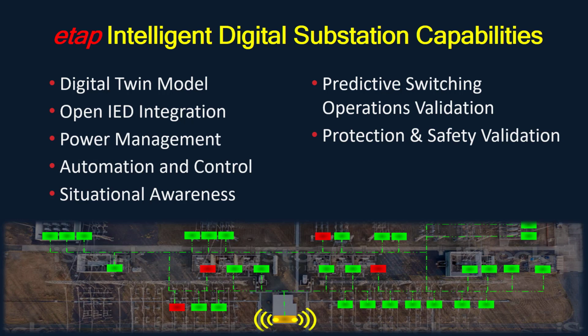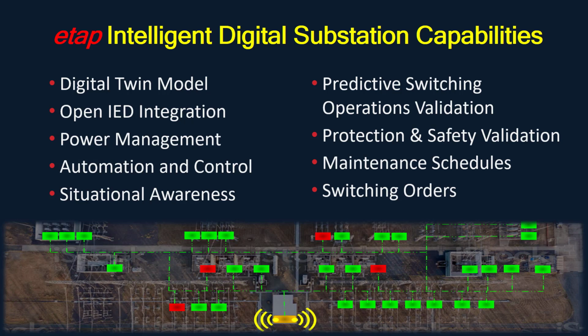Protection and safety validation is also included. This gives you a common platform that allows you to collect all the settings of all the different devices in the system in one common place. From there, you can do safety validations, you can check setting changes, you can look at historical logs, and get a complete picture of where the protection system is at the substation level. You can also access maintenance schedules and switching orders.